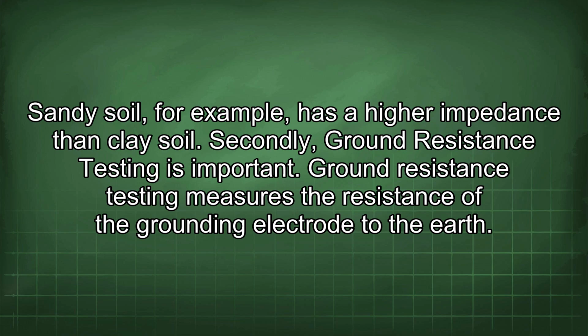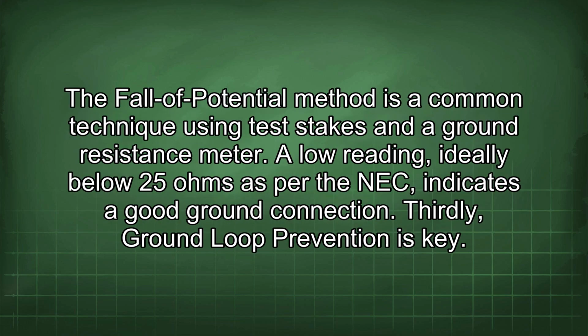Secondly, ground resistance testing is important. Ground resistance testing measures the resistance of the grounding electrode to the earth. The fall-of-potential method is a common technique using test stakes and a ground resistance meter. A low reading, ideally below 25 ohms as per the NEC, indicates a good ground connection.